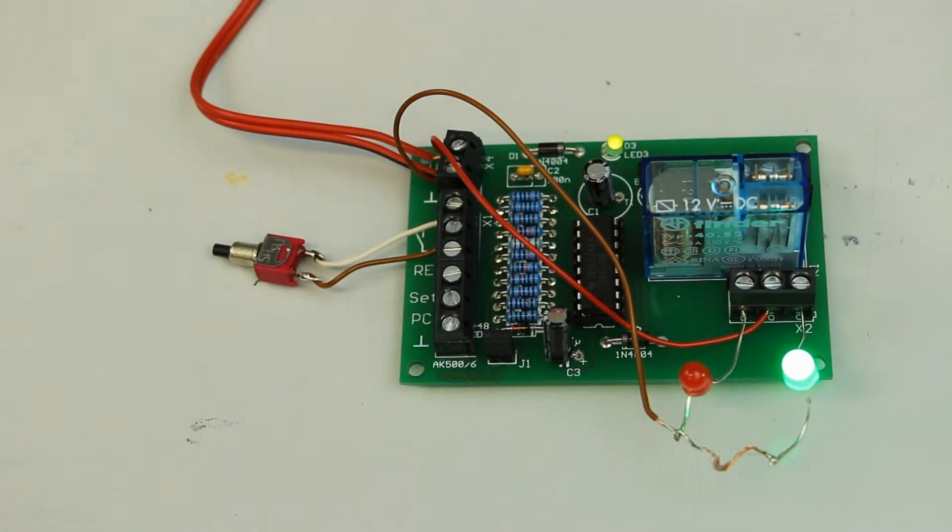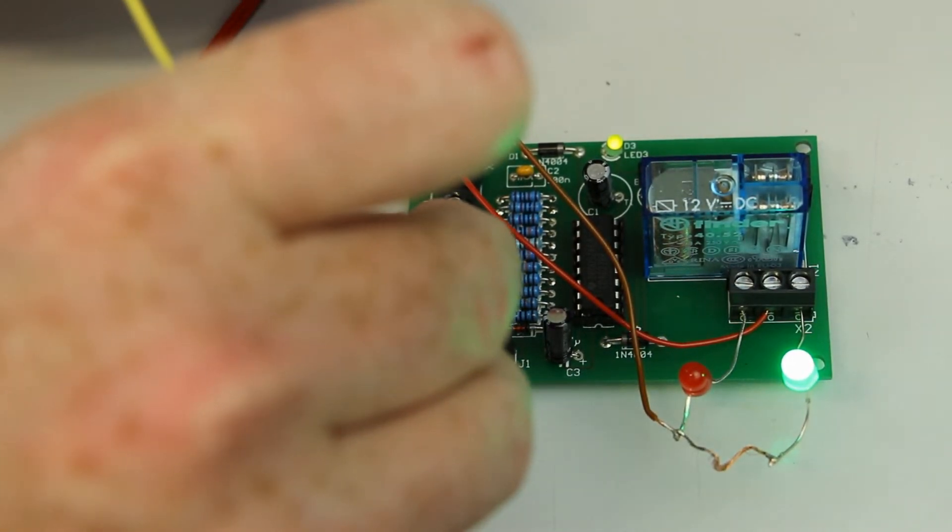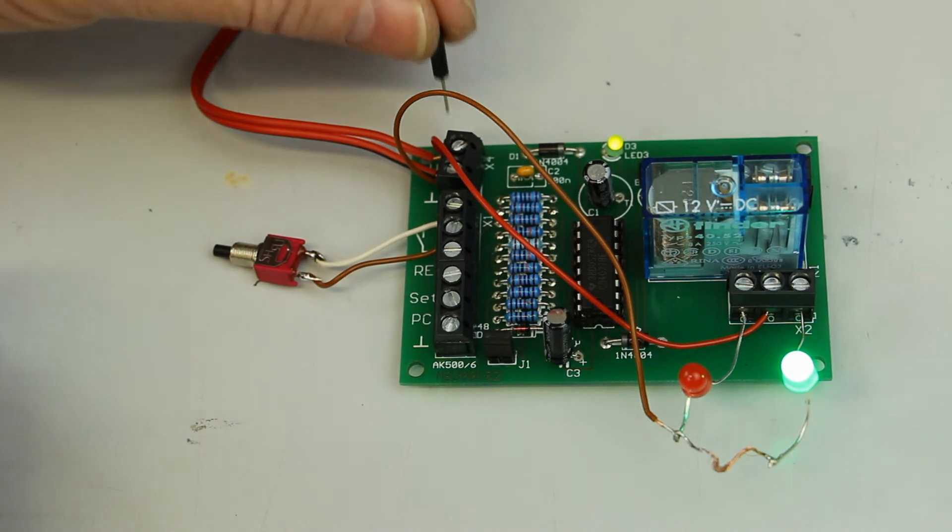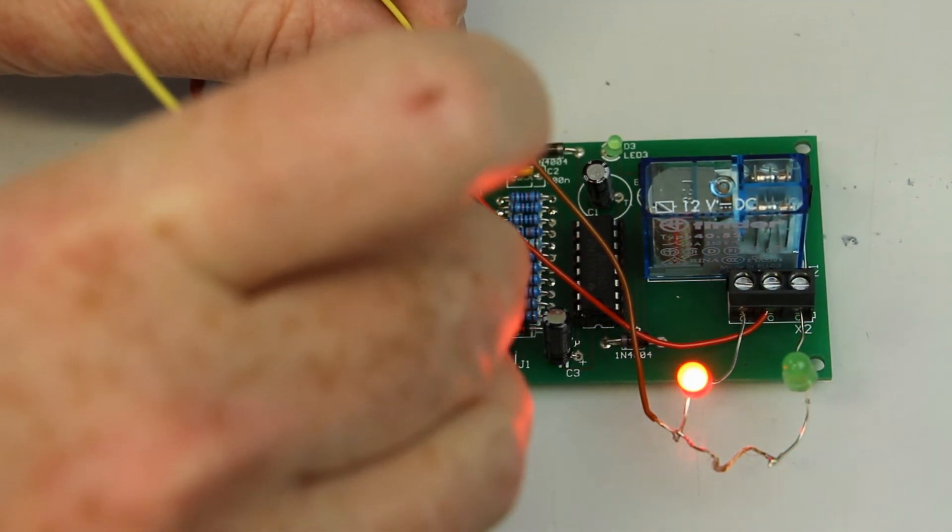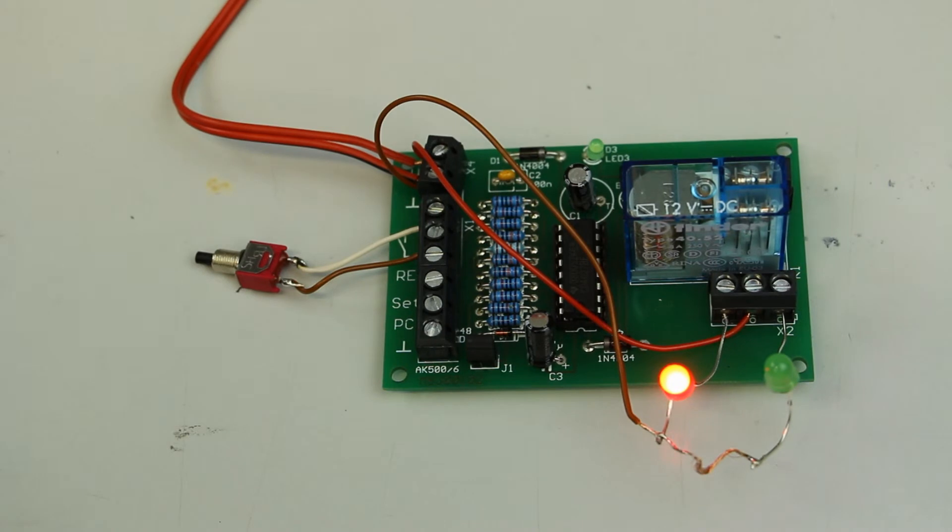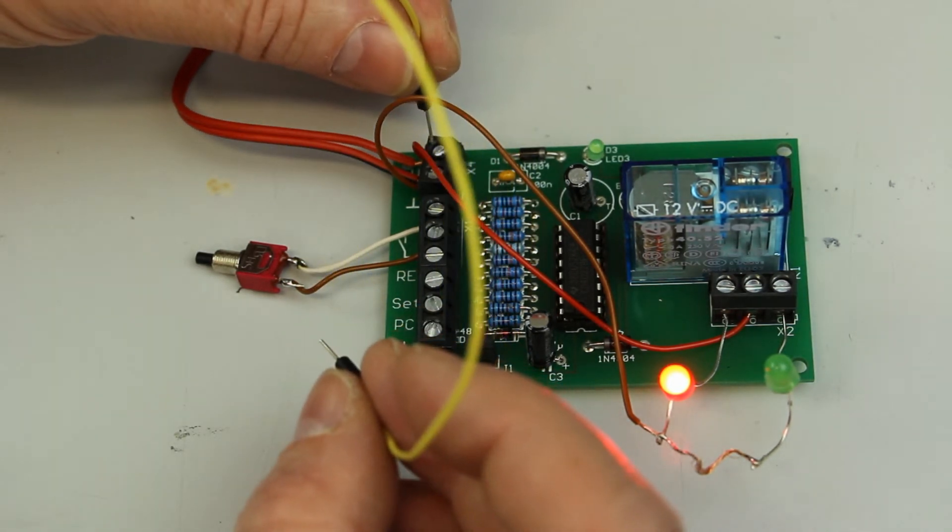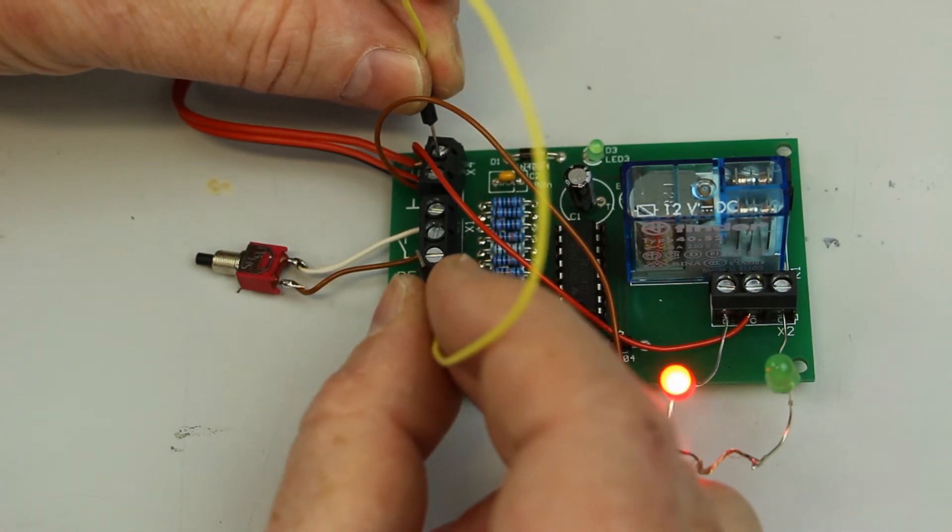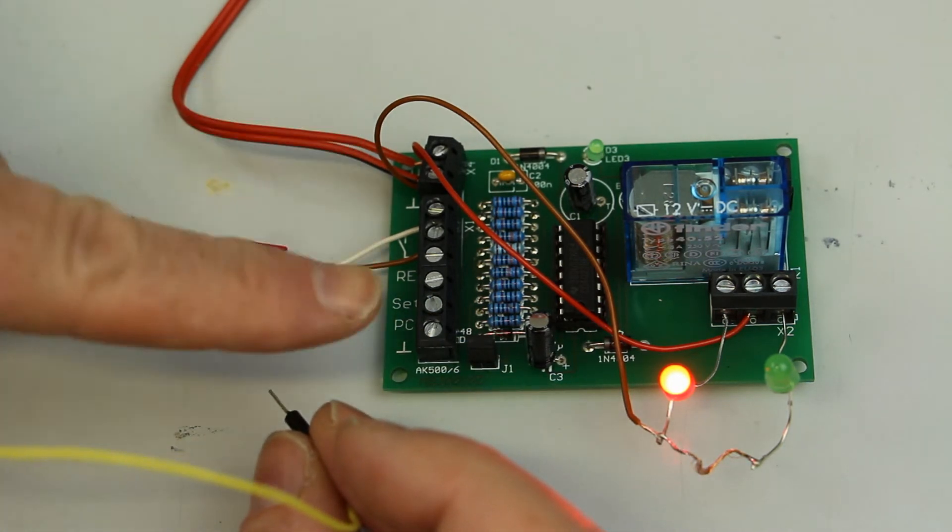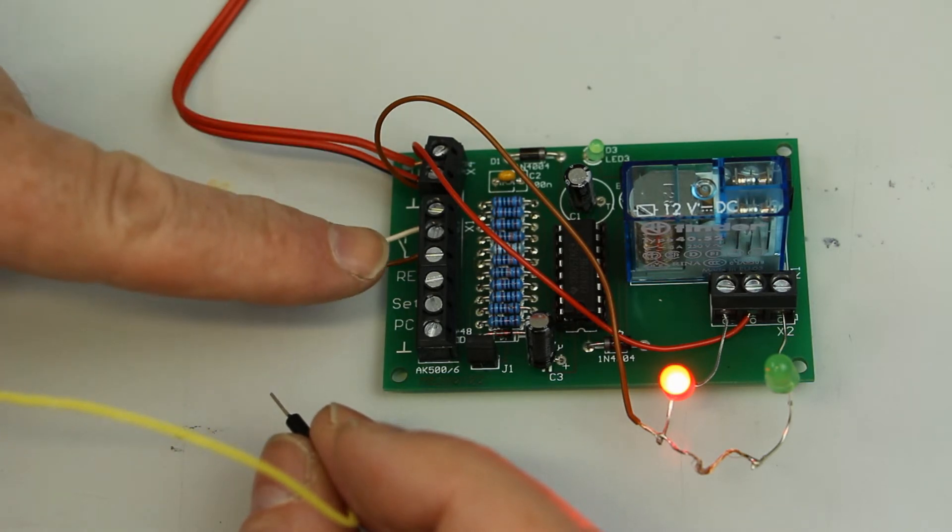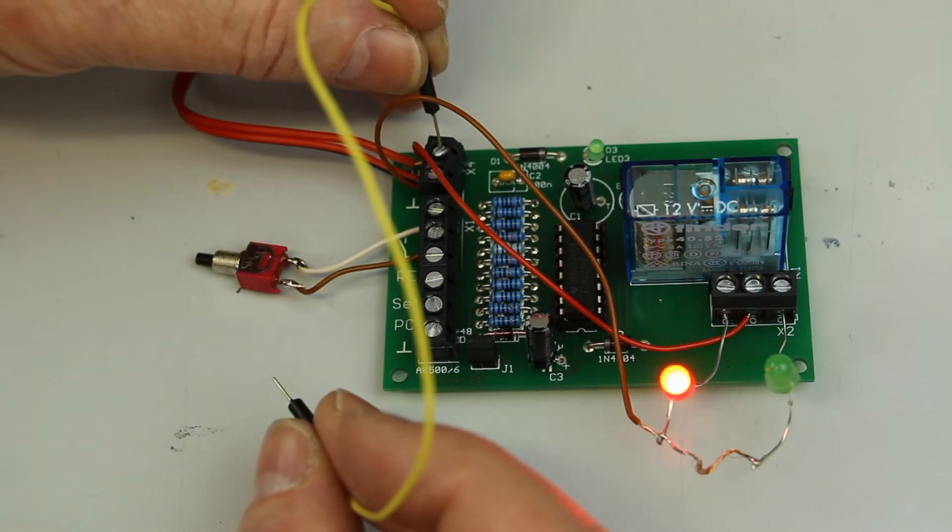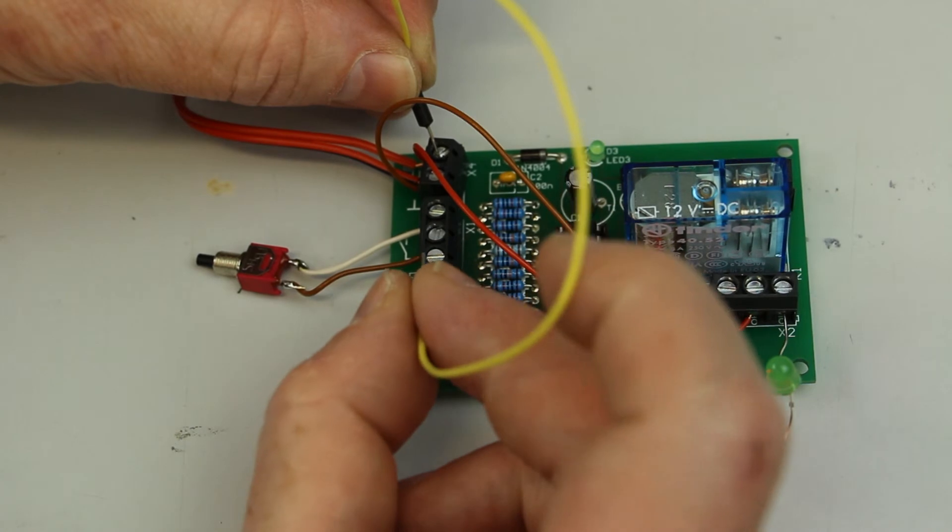Now what happens when we activate or connect the reset input with the plus side? Well, whatever state the UNIREL was before, after activating or after putting a positive signal, either directly with a push button from the power supply or from an external signal—as long as it has the same voltage or higher because we have protection against higher voltages—so if you feed a signal with in this case 12 volts or higher to the reset input, the flip-flop will always set the relay to the off state.